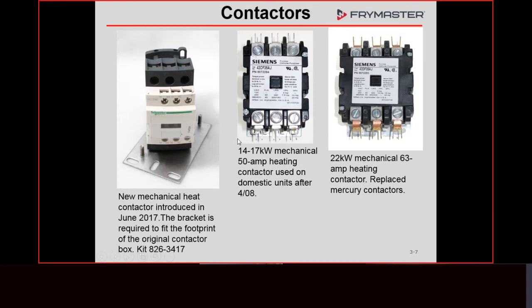The option that we chose at the time, and some of you guys in the class now ask, why don't you use solid state relays? Why don't you use this or that? Solid state relays we actually have used in fryers before, and the lifespan of those doesn't meet what a Mercury contactor was. It's really not much better than what the mechanical contactors were. Plus, they take up a lot more room because they produce so much heat. You have to have big heat sinks. The cost of them is very high.